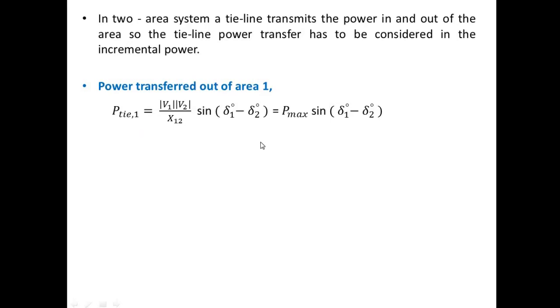In practice, we should not bring the voltage angle to 90°, because at that point the tie line loses its rigidness, or stiffness. To maintain the rigidity of tie line power, we always maintain the angle between 30° and 60°. This is an important practical constraint from the tie line power flow relation.